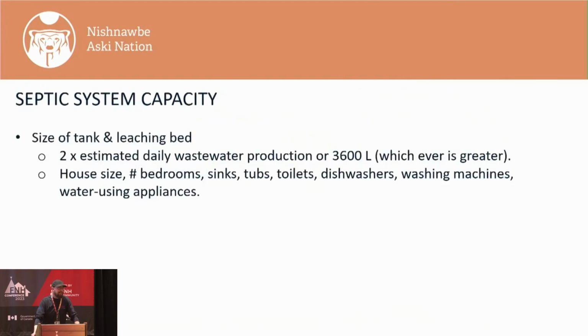So, septic system tank capacity, this is always a tricky issue with people. Capacity for a septic tank is not defined by how many people live in the house. Tank capacity is defined mostly by how many bedrooms there are. After that, there's a calculation related to the number of total fixture units in the dwelling, but also additional house area.